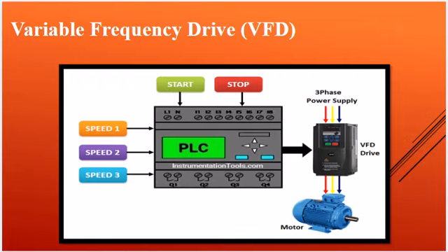Unlike traditional throttling methods, VFDs reduce energy consumption by slowing down the fan motor instead of mechanically restricting airflow. This results in significant energy savings, particularly in systems where the fan operates below full capacity for extended periods. VFDs also minimize mechanical wear, extend equipment lifespan, and reduce noise levels. They are widely used in HVAC systems, industrial ventilation, and cooling applications, ensuring optimal performance and lower operational costs.